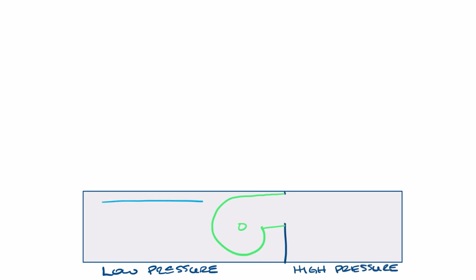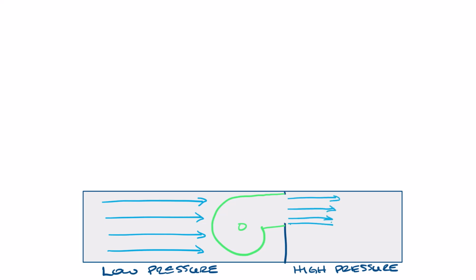So I'm going to start by just looking at a fan in ductwork or in a cabinet and mounted on a discharge panel. This side is the low pressure side, and over here on the discharge side of the fan is the high pressure side. The air is drawn fairly evenly into the fan inlet on this side. But the airflow out of discharge looks like this, with a higher velocity up here where the air is moving out of the fan, and eventually the airflow profile will spread out to fill the ductwork.